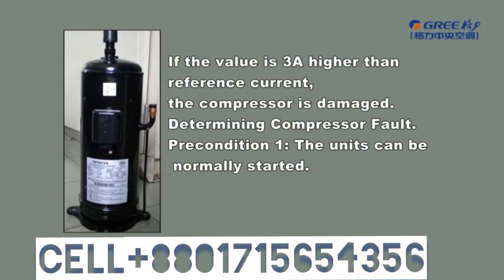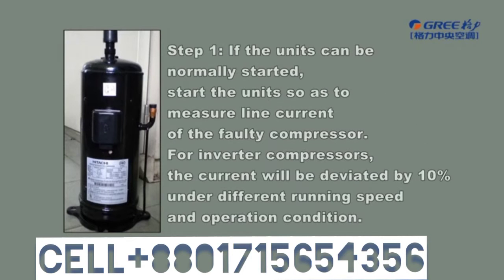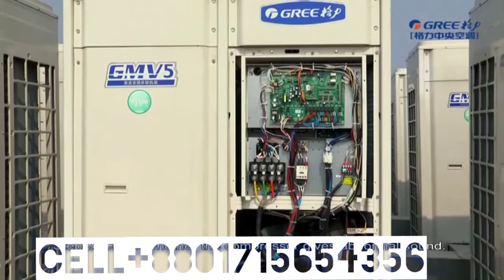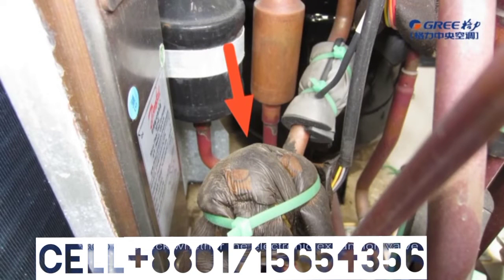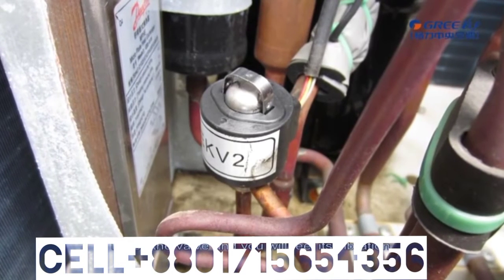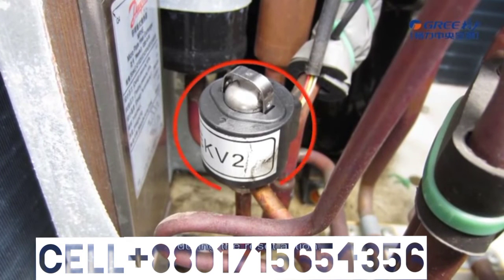Determining compressor fault. Precondition 1. The unit can be normally started. Step 1. If the unit can be normally started, start the unit so as to measure the line current of the faulty compressor. For inverter compressors, the current will deviate by 10% under different running speed and operation conditions. Step 2. Check whether the compressor gives abnormal sound. Step 3. Check whether the electronic expansion valve of the outdoor unit works properly. Touch the valve and you will feel its vibration during the reset action. A crack sound will be heard as well.